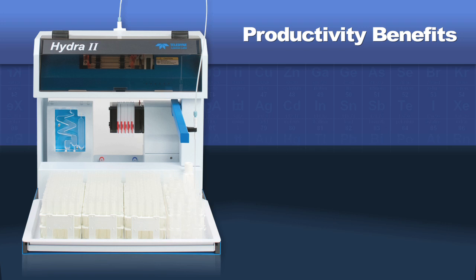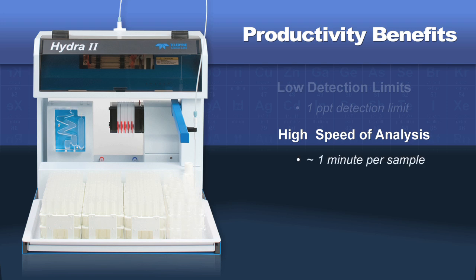Central to the productivity benefits of the instrument are its low detection limits, one part per trillion, and high speed of analysis, approximately one minute per sample.